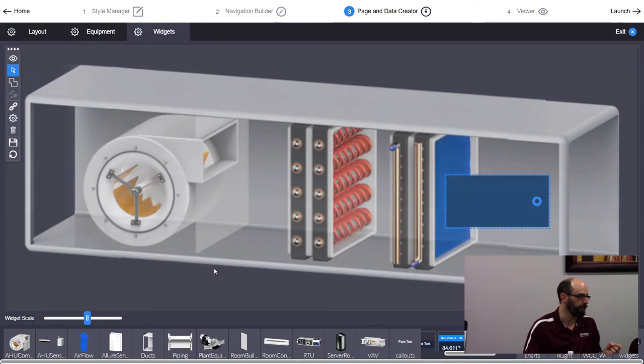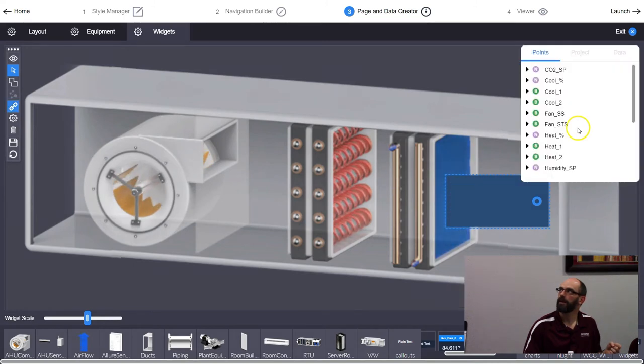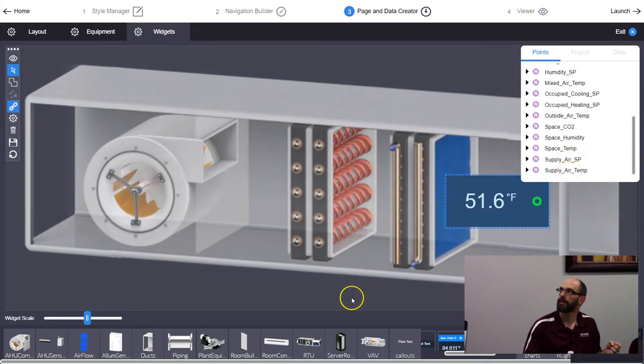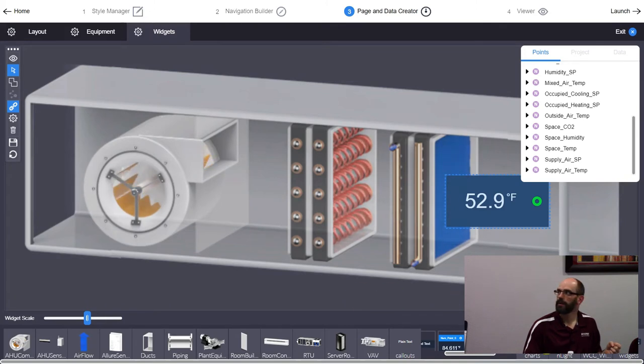When you're pasting a widget, make sure you're on the Widgets layer; for equipment, make sure you're on the Equipment layer. When it's on the wrong layer, it doesn't work right. To bind a point, hit Find Data and search for your supply temp — drag it on. That's one point.